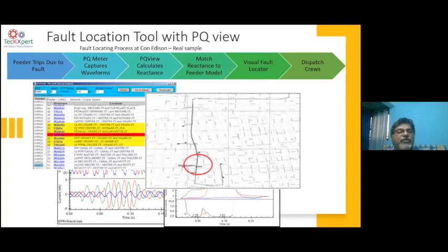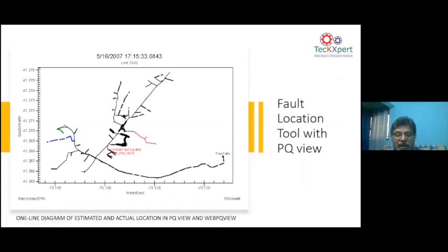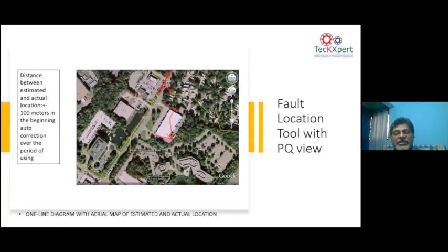For example, when a fault happens, you can see on the screen a waveform which is captured by the PQ meter, and it is also displayed as an event in an event list. You can see this is the event, and this is how the voltage waveform is. Then the software calculates the reactance to the fault, matches it with the feeder model, and then you can visualize the fault. This is a feeder model, and you can visualize it on a Google map.